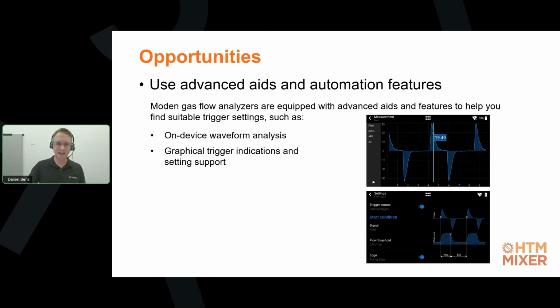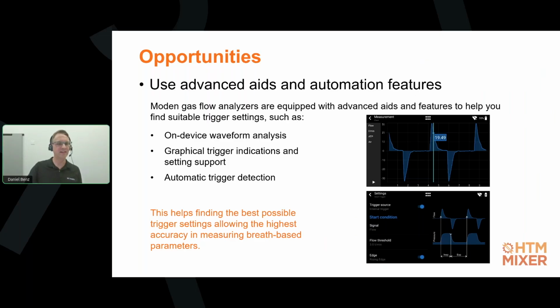And the latest gas flow analyzers even offer smart automatic trigger detection. They analyze the flow and pressure waveform automatically in real time and then determine optimal trigger settings for you and set them accordingly. Just imagine how helpful that will be in the situation we discussed earlier with the BiPAP ventilator, where we have to adjust our trigger levels based on the settings on the ventilator. These features help you find the best possible trigger settings and allow the highest accuracy in measuring breath-based parameters.